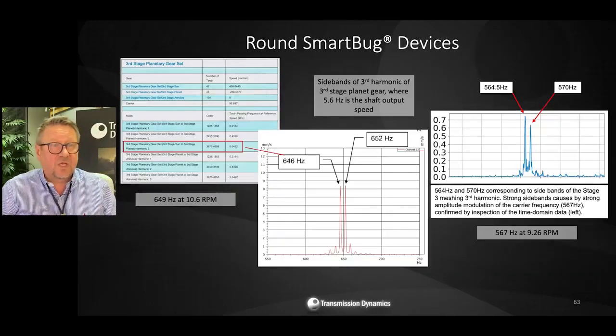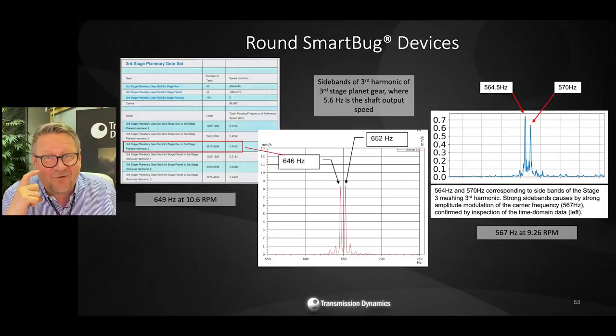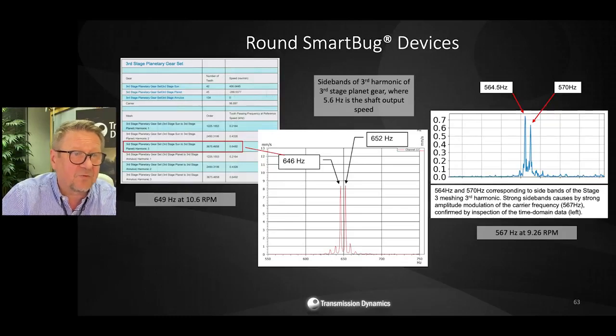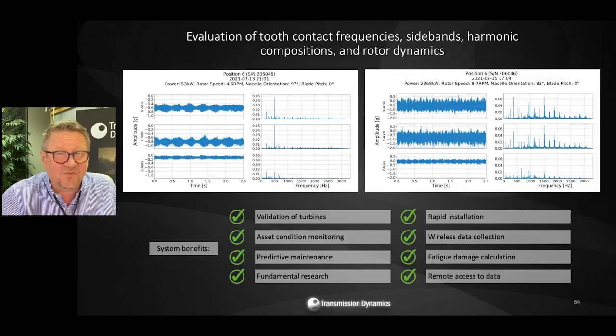So, when we have the very heavily modulated signal as a carrier frequency, and the amplitude modulation is reaching around 100%, so when the amplitude goes to a maximum and then diminishes nearly to zero and goes to the maximum again, the frequency spectrum of the 100% amplitude modulated signal is such that we see the right and left hand sideband where the carrier frequency, tooth contact frequency on this occasion, diminishes and disappears completely. So we can only see the sidebands in this application. Now the multiple sidebands are typically a characteristic of phase modulation, so it's good to remember that.